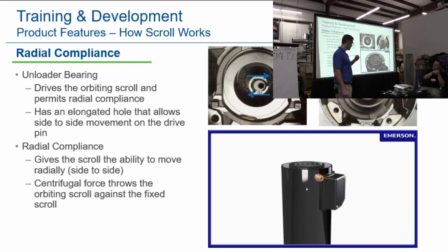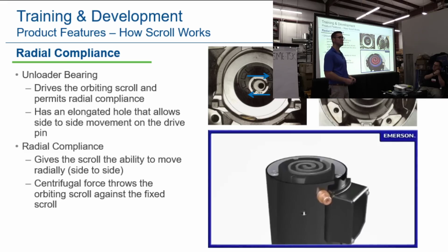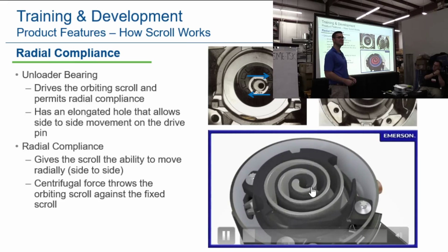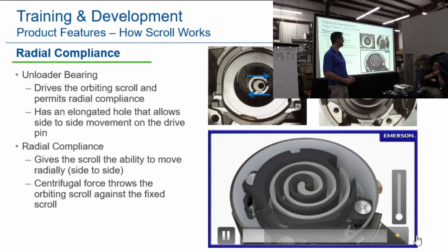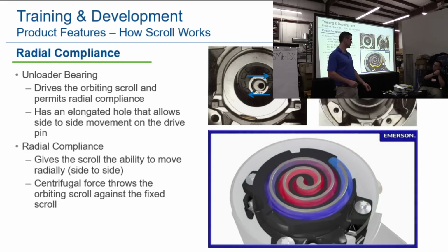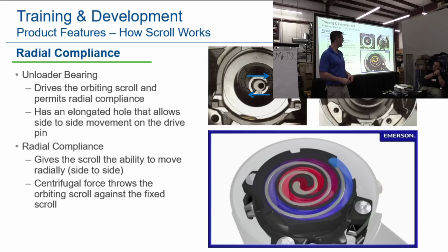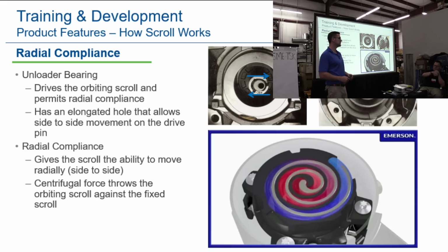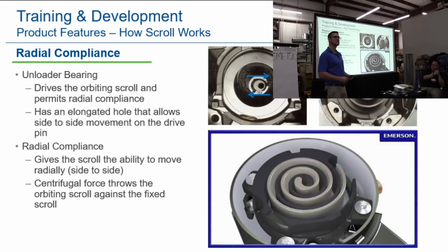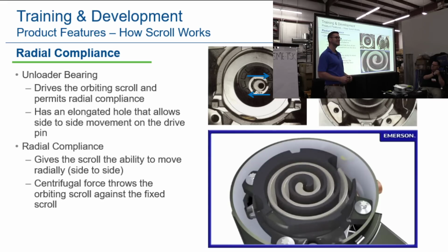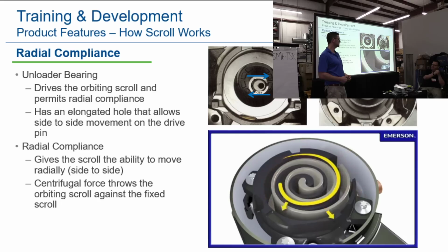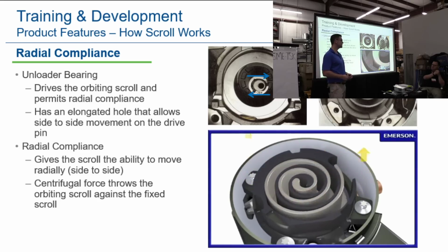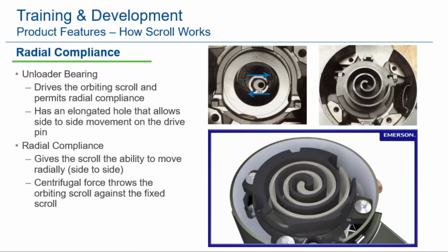During periods of cool weather, refrigerant can condense in the gas lines of HVAC systems, eventually migrating into the compressor. A key feature of the Copeland scroll compressor is its ability to handle liquid refrigerant with its compliant scroll design. During normal operation, radial contact between the two scrolls is held tight by centrifugal force acting outward upon the orbiting scroll. Axial contact is maintained through positive pressure differential between the stationary and orbiting scrolls. In the event liquid refrigerant enters the scroll cavity, the radial and axial compliance allows the scrolls to separate, safely passing the liquid out of the scroll cavity without damaging the compressor.